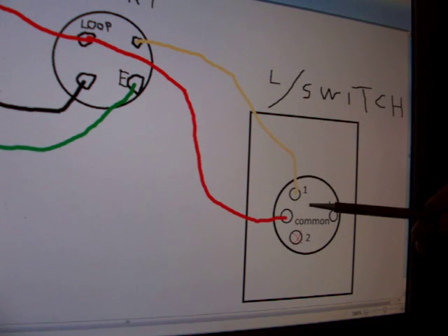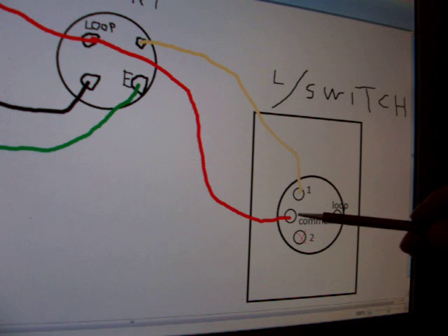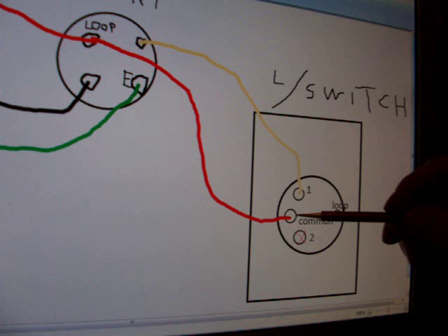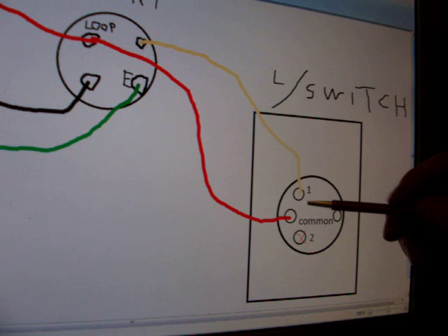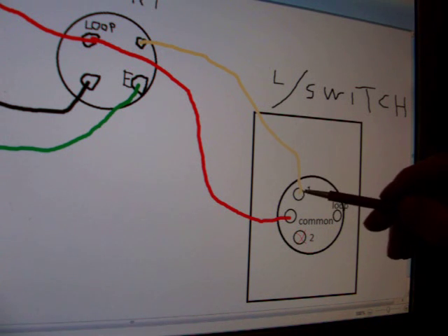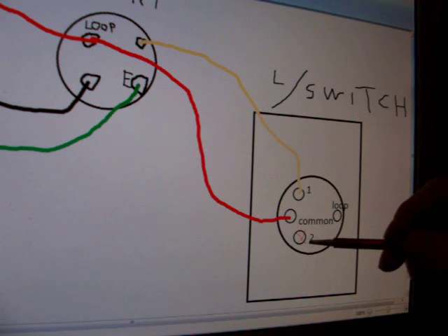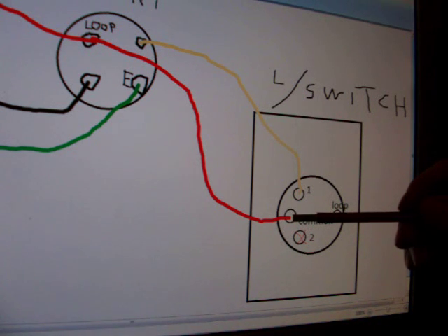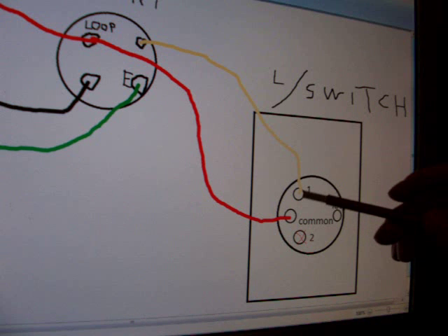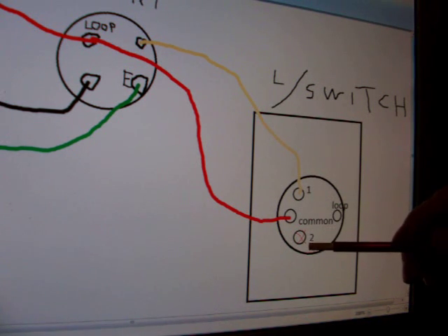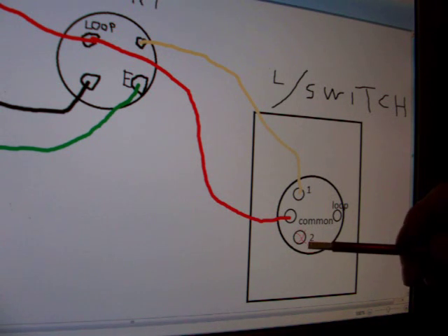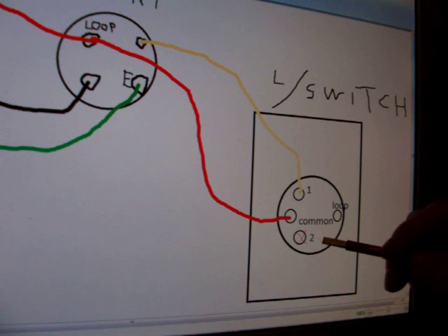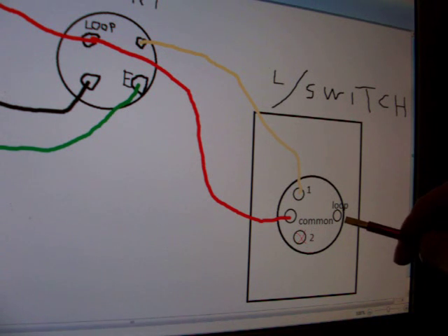Anyway, your active continues down to the switch. The switch has a terminal called common. Now common connects to a little plate inside the switch. And when you flick it, whichever way you flick it, let me review the terminals. You've got common, loop, terminal number one, and terminal number two, which may or may not be labeled. Your active goes to the common terminal. And depending on which position the switch is in, it's switching common between either terminal one and common, or common and terminal two. Now terminal two generally has a plastic X through it, which I've put a red X through it to represent that it's normally blocked off. That makes wiring up a lot more simple because you can't confuse it with a loop terminal, for example.